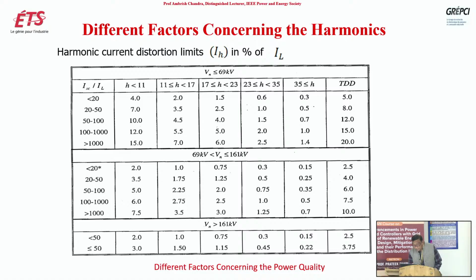So if the system short circuit current divided by load current is 20, then instead of 4 you have 2 here, instead of 7 you have 3.5 here, instead of 10 you have 5 here, so half of these, 15 becomes 7.5. Same thing for other ranges also, this is half, instead of 2 you have 1. Almost going half of all those values. So if the voltage level is increasing, you have to have more severe limitations on harmonics, and here you can see also half TDD total: instead of 8 you have 4, instead of 12 you have 6, instead of 15, 7.5, instead of 20 you have 10.